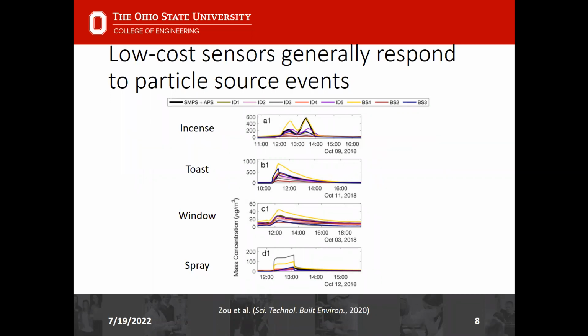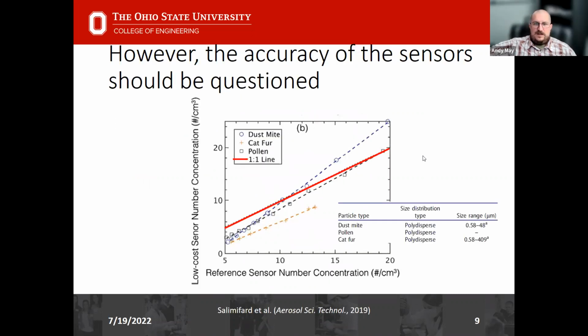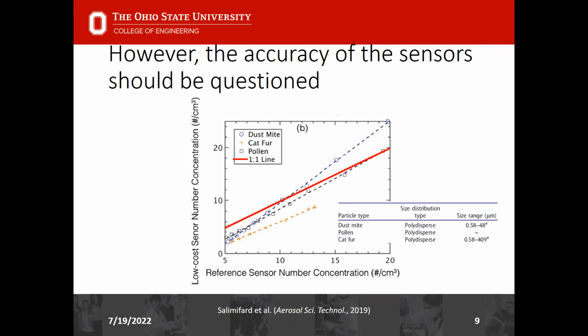So you're basically suggesting, if we have something like this, where we have a fairly linear response, the R squareds are likely high here. I don't know what they actually are, but we know there's linear regression, so we could use that as a calibration equation. Is that what you're suggesting? Yes. Yeah. So I think, and this is maybe something that it should have been explicit in saying, we think that if you have a more precise sensor, it's more likely that you can come up with those calibration equations and have those calibrations be more reliable as you apply them, because you're not dealing with that imprecision that could affect those calibrations.